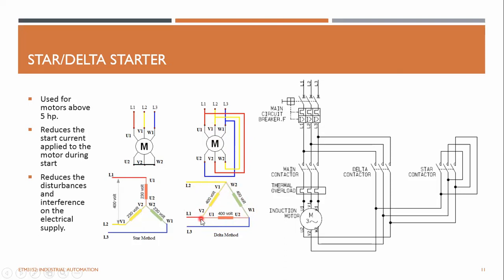So when it is a delta connection, the line to line voltage is 400. So full voltage is applied across the coils, allowing a large current to be drawn. This is not good initially. So initially you supply it as a star connection. Then you switch to delta connection once the motor reaches steady state and full speed, and get the torque that is required.